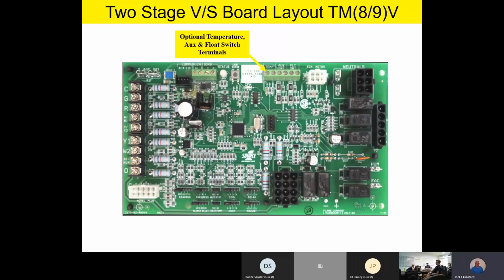Now, if you have a communicating system, you'll notice there's another green terminal block here. If you have a communicating system, we give you some optional terminals to hook up some accessory devices. Because remember, if you've got a communicating system, it's just a 4-wire hookup. But you have some optional temperature switches, auxiliary, and float switch terminals. If you want to have an auxiliary float switch, for instance, instead of just cutting power to the board like you normally would, or like some wiring schemes, you just shut the power off if you have a float switch issue, or you kill the Y terminal if a condensate float switch trips off, it kills the condensing unit outside.